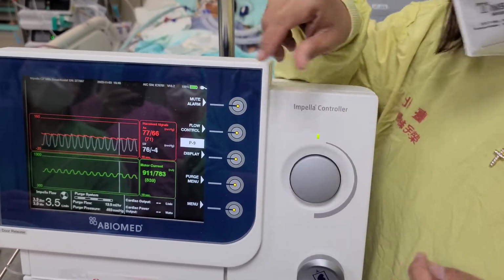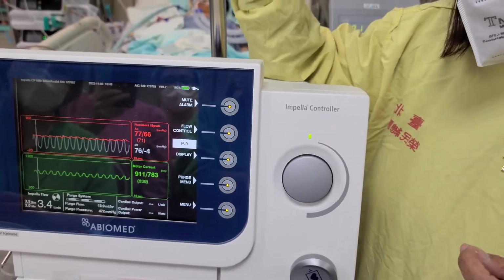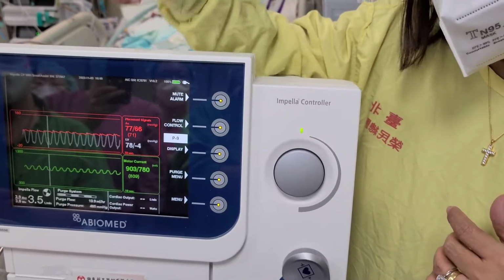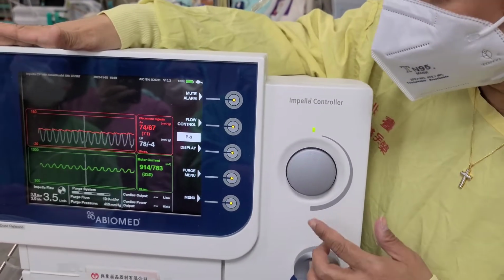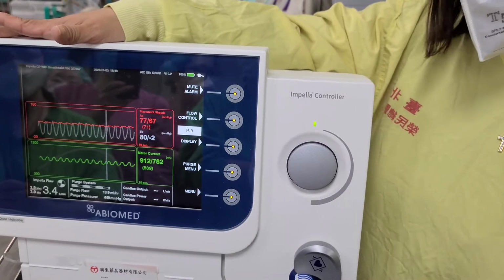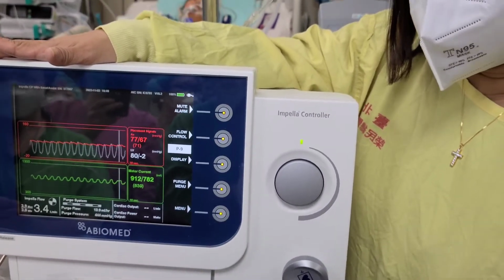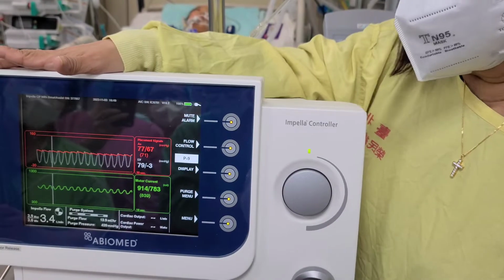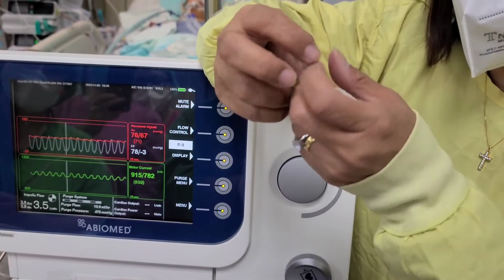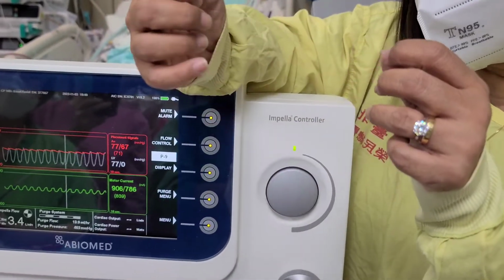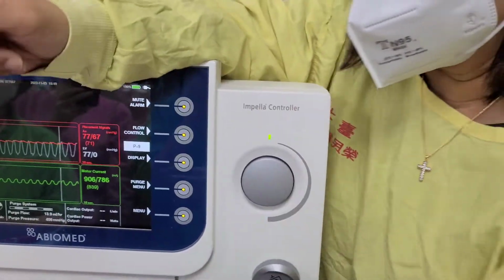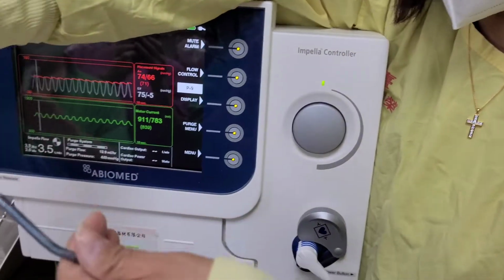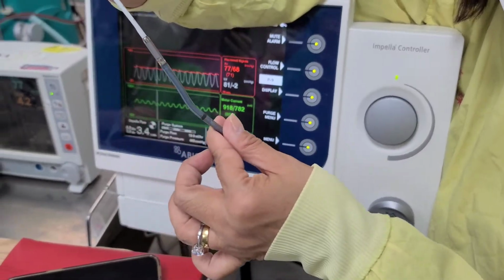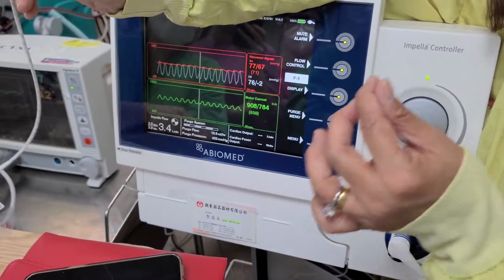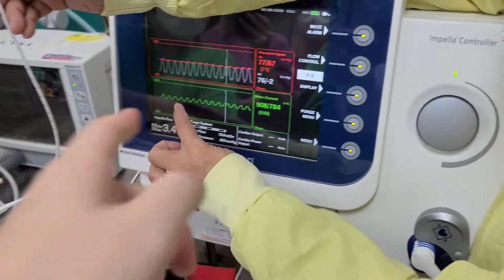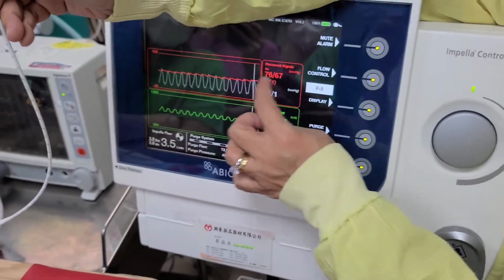Make sure that the ACT is below 150, number one. Number two, at P2, they will remove the stitch that secures the sheath to the groin, loosen the connection and pull the Impella out. For example, the Impella is like this, right? They will be pulling it out of the aortic valve. How will you know? Your motor current waveform will be flat and you will only have an aortic waveform.